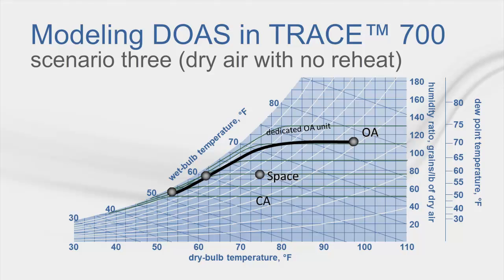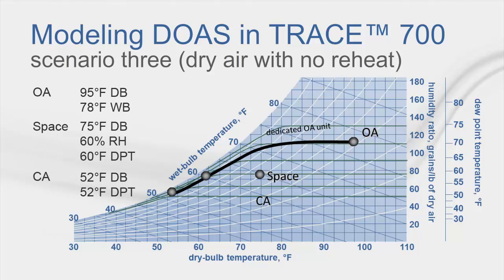Looking at the psych chart during the cooling design day, the DOA unit cooling coil dehumidifies the outdoor air resulting in a dew point that is drier than the space. Since this DOA has a controller with dew point optimization, the dew point leaving the DOA can float up to 60 degrees dew point while maintaining adequate humidity levels in the space, which is set to 60% in this scenario.